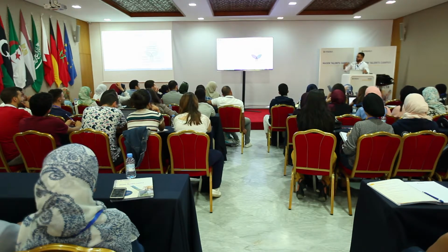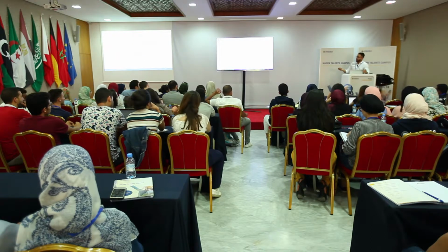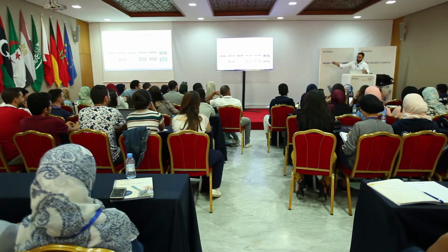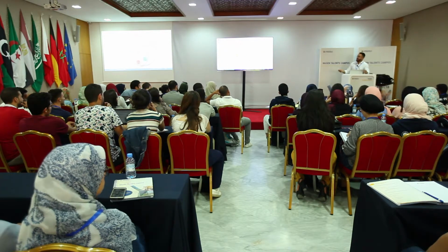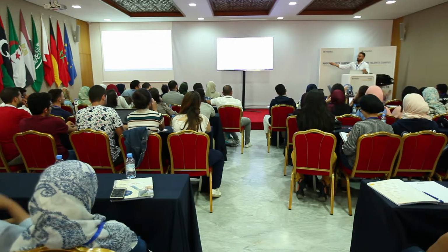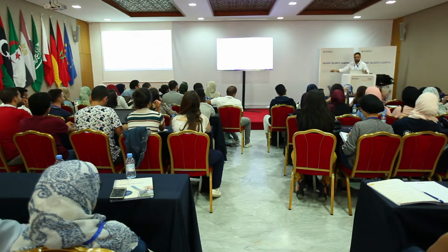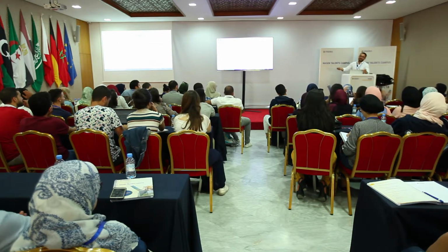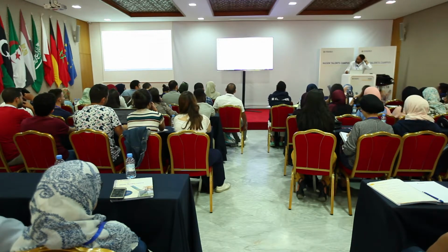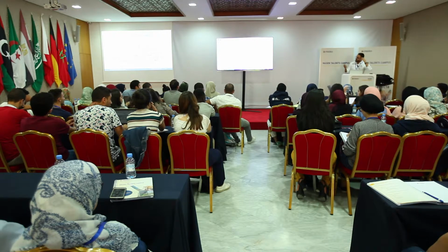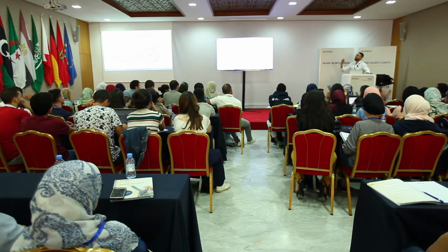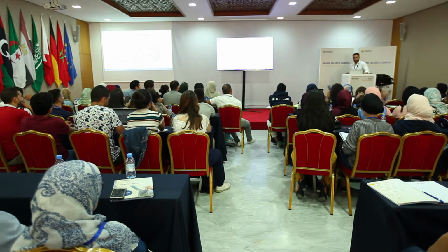If you start comparing the LCOE of a PV with a CSP, and you tell me, yeah, the LCOE of PV is better because it's $25 per megawatt hour, and the LCOE of CSP is 70 or 90, then yeah, that's true, but you're comparing pears to apples. Again, the whole purpose of today is that you realize that they have a different value. So you should compare the CSP with another plant that is able to deliver 80% capacity factor, that is able to provide electricity at 9 p.m., because they serve a different purpose.